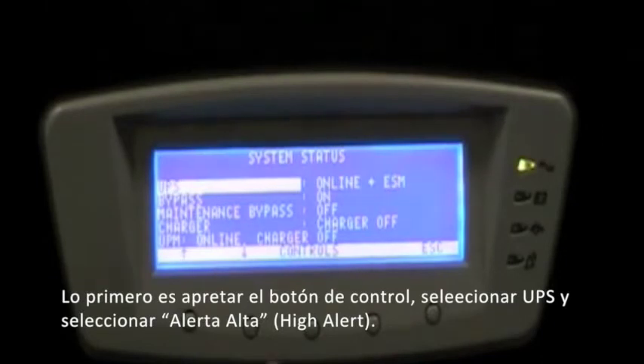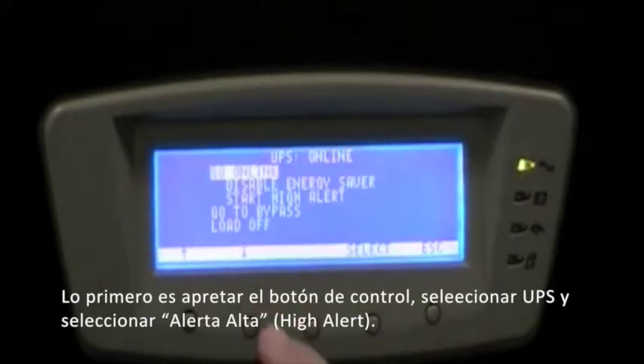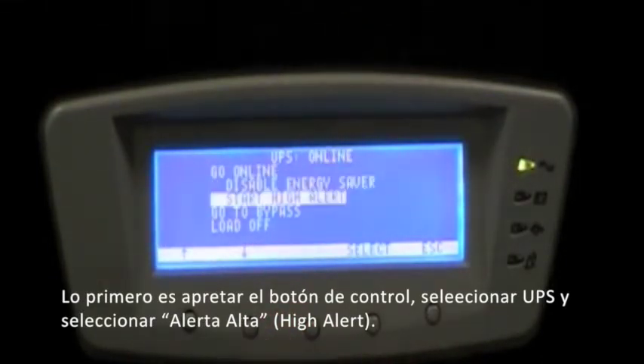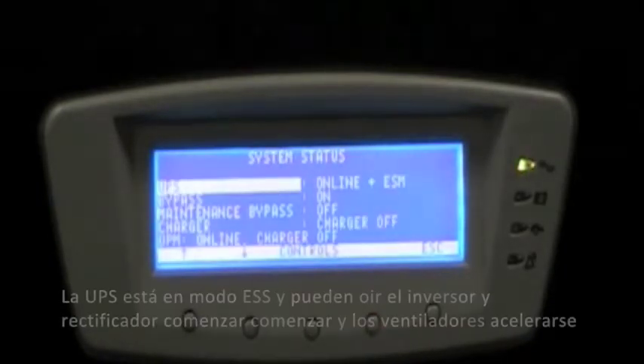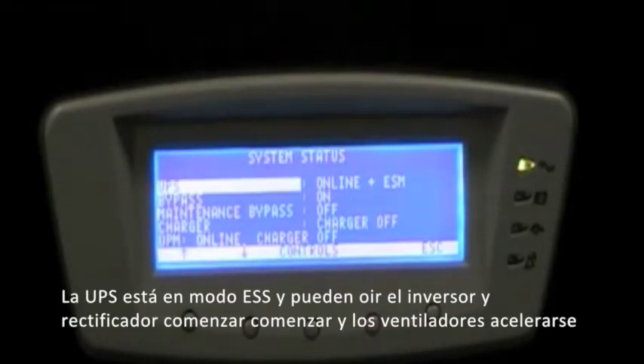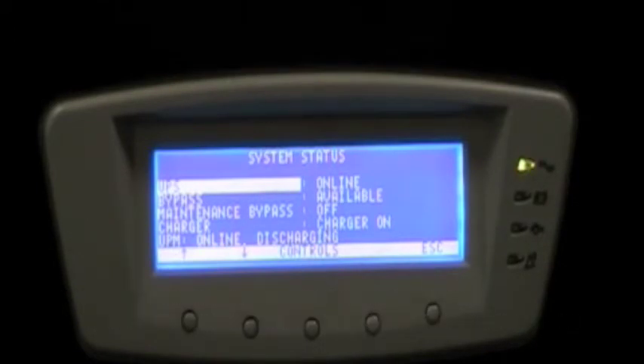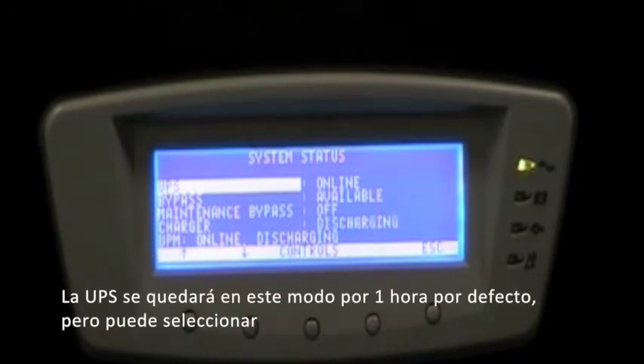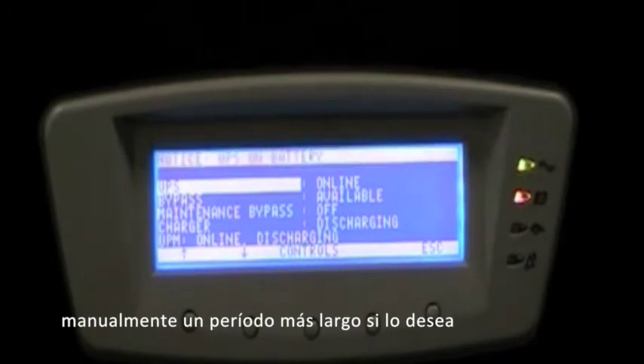First step is to press the control button, select UPS, and select Start High Alert. The UPS is currently in ESS mode, and you hear the inverter and rectifier start and the fan spin up. The UPS will remain in this mode for 1 hour as a default. You may select a longer time for high alert mode if desired.